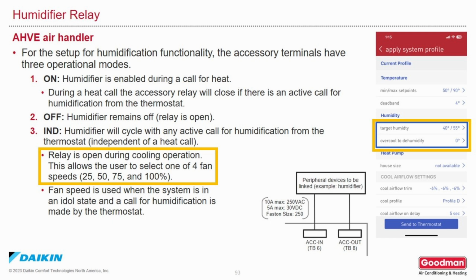This allows the user to select one of 4 fan speeds, 25, 50, 75, or 100%. The fan speed is used when the system is in an idle state and there is no call for heat, but there is a call for humidification made by the thermostat.